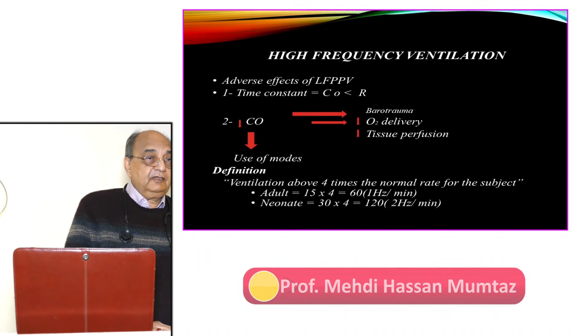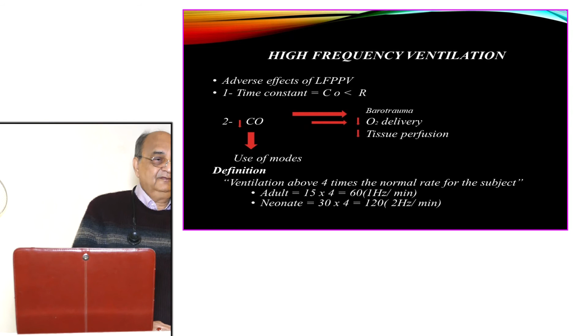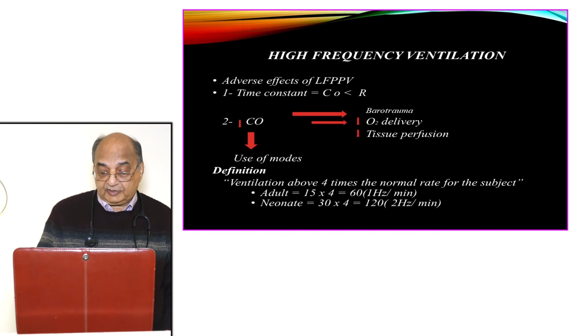In an adult, it is a rate of more than 4 times the normal rate. For example, if you are breathing 15 times per minute, multiply by 4. If you are ventilating 60 times or more, this is called high frequency ventilation. In the case of neonates, the normal rate is about 30, and high frequency ventilation will be, if you multiply it by 4, at least 120, more than 120. So that we label it as high frequency positive pressure ventilation.